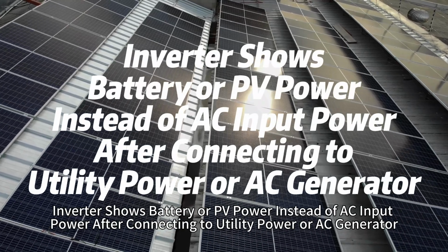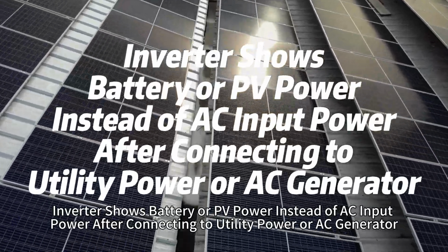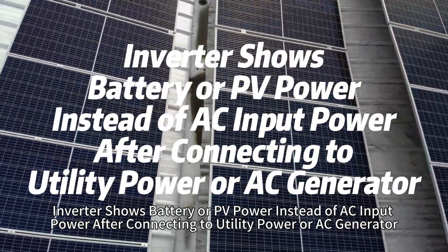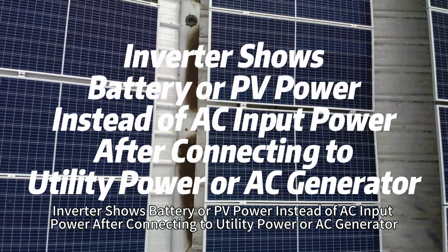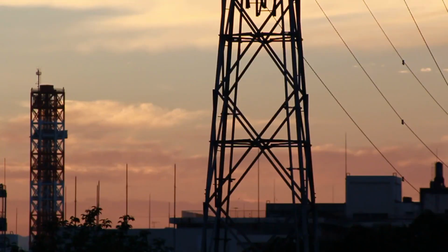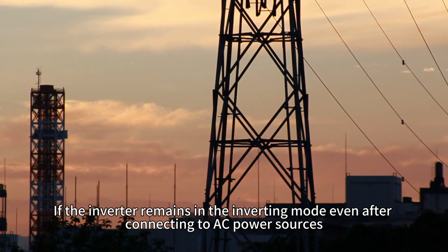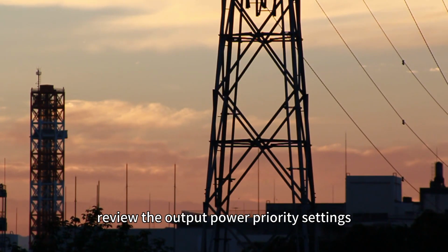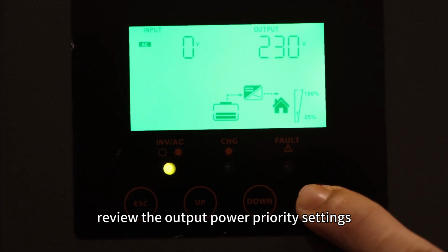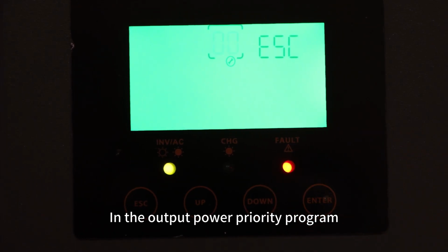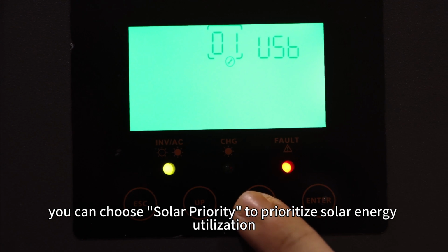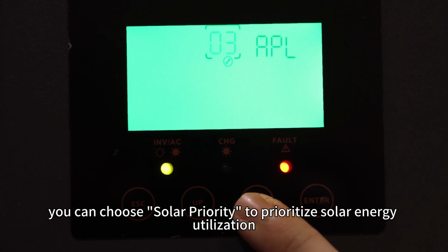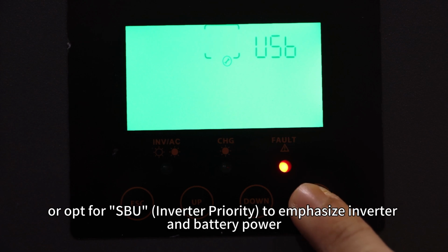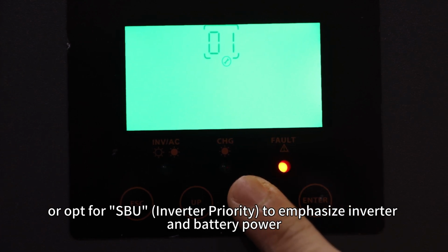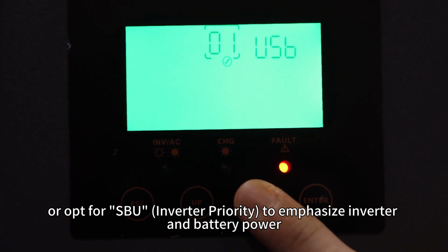Inverter shows battery or PV power instead of AC input power after connecting to utility power or an AC generator. If the inverter remains in the inverting mode even after connecting to an AC power source, review the output power priority settings. In the output power priority program, you can choose solar priority to prioritize solar energy utilization, or opt for SBU to emphasize inverter and battery power.